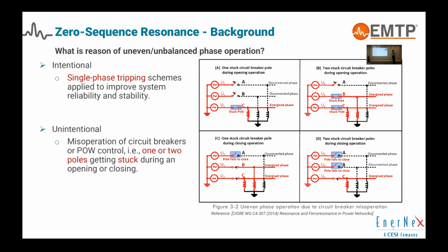The question is, why unbalanced phase operation? It can be intentional or unintentional. Intentional is when single phase tripping schemes are applied to improve the system reliability and stability. And unintentional operation would be, for example, if the breaker is supposed to open, but it remains stuck. So there would be unbalance.